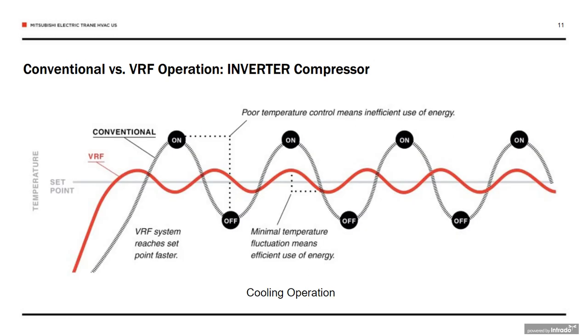If we look a little deeper into the differences, for most cooling systems, the heart of the system is the compressor. Here you see the compressor on the graph for a VRF system in red and a conventional system in gray. The conventional system first will modulate by turning on and off to satisfy the space temperature. When the system is off, there's nothing happening. There's no cooling, there's no air filtration, there's no air movement, and this leads to the temperature swings off of the set point that you see shown.